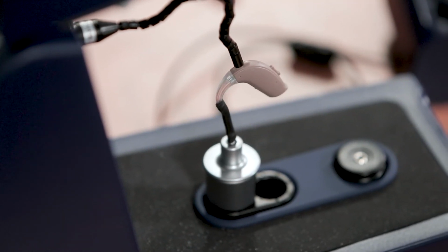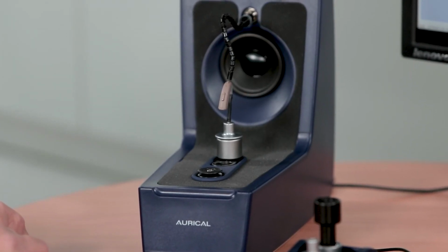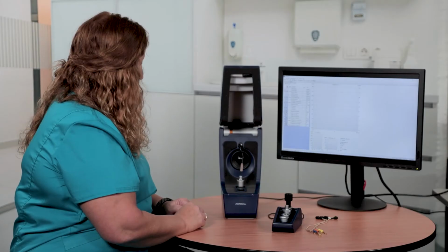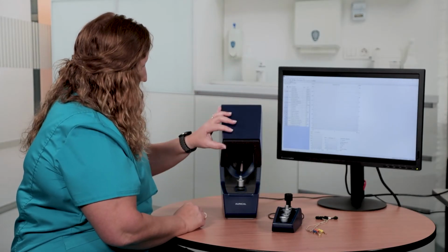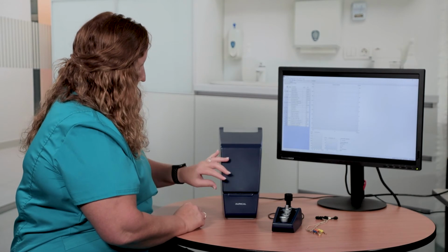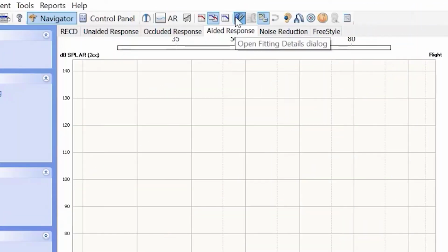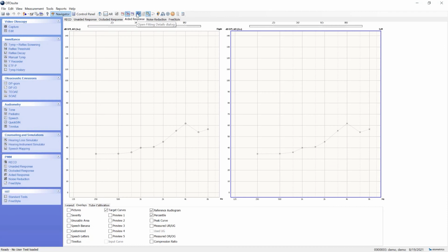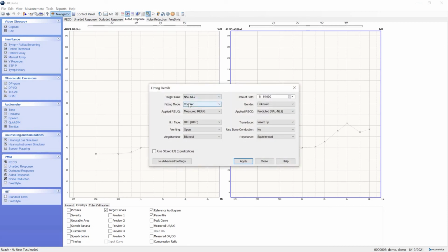Once you have the hearing aid set up in the Aurical HIT test chamber, conducting a coupler-based fitting is as simple as changing a few options in your normal real ear measurements procedure. Open fitting details by selecting the blue hearing aid icon in the toolbar, or by pressing F10 on your keyboard. In the fitting details box, be sure that fitting mode is set to coupler. This prompts OtoSuite to connect to Aurical HIT instead of Aurical FreeFit.